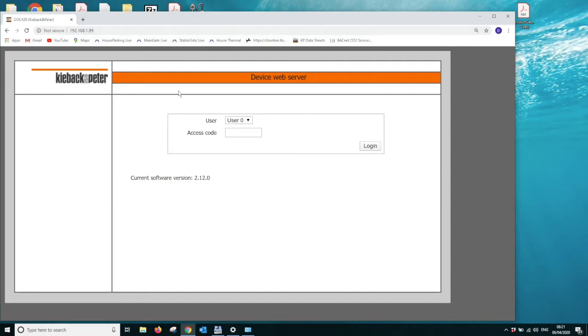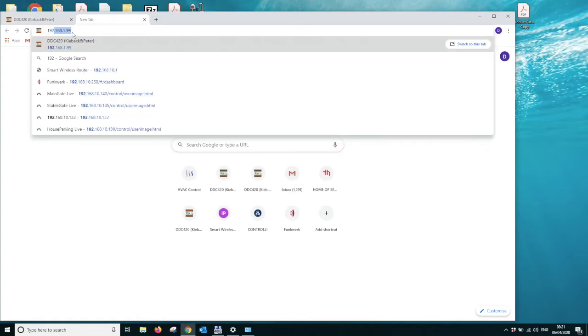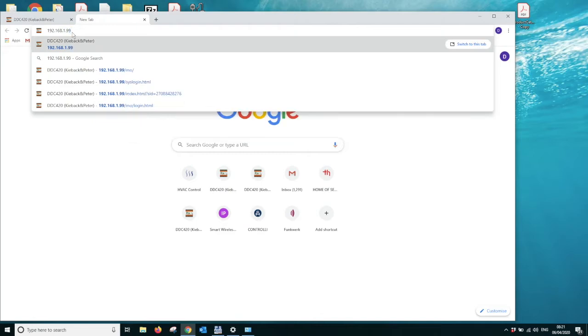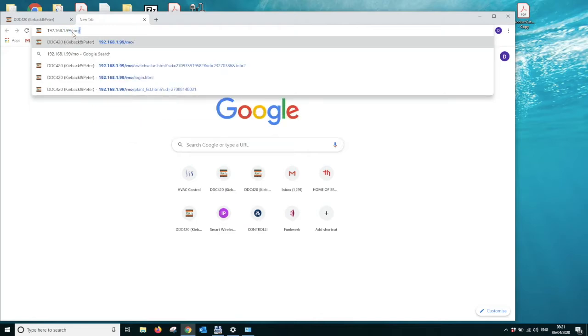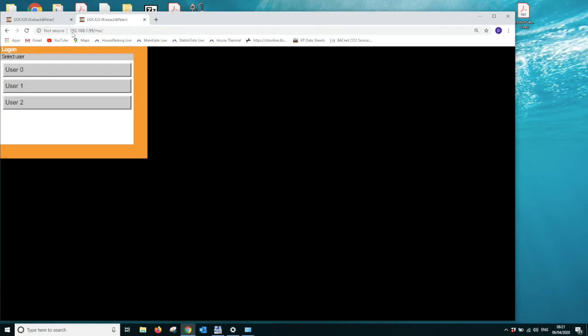We can choose to use the default web browser, which is the one you can see on the screen now, or we can set the controller up using a different web browser connection by entering the same IP address 192.168.1.99, and this time put /mo/, and we end up with the modified user interface, which is designed for the touchscreen. Some people prefer it because it's a little bit more user friendly, a little bit more attractive to look at. There's no difference between the two web browsers, but we'll use the MO one for now.